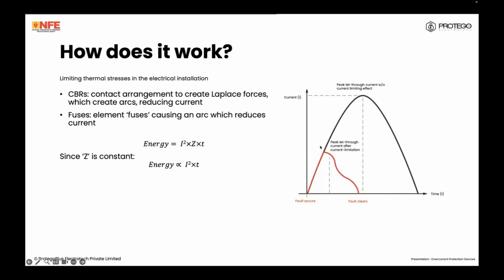Now, if we look at the waveform of current versus time, let's just see. We all remember from basic high school that energy is equal to I squared times R. We use impedance here instead, Z times T. Since the impedance when a short circuit happens is constant, we've assumed it to be constant. Energy is directly proportional to I squared T, which is our let through energy. So I plotted current against time just to give us an idea. As the current increases, the energy increases as the square of that.